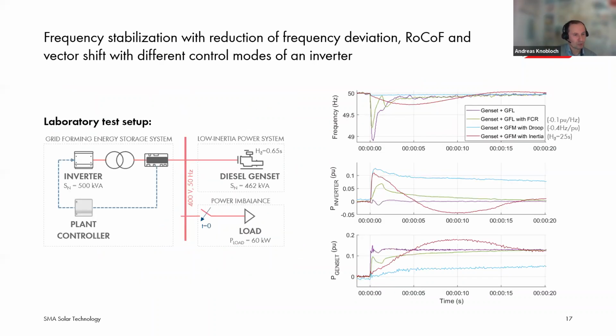We did some laboratory tests within one of our research projects. It was Grid Control to Zero. Maybe you've heard about it. We also published some papers on that. The goal of this test was to show how different control modes of an inverter impact the frequency stabilization in a low inertia power system. How do they impact the frequency deviation, the rate of change of frequency, and the vector shift when we operate the inverters in different control modes?